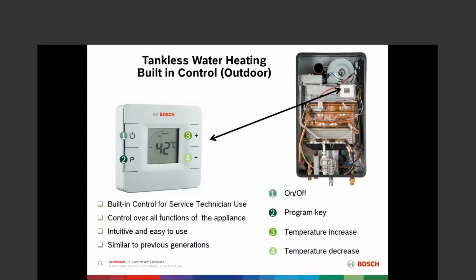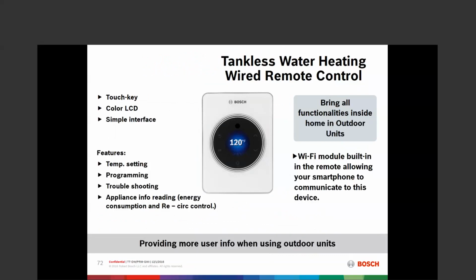This is the control on the outdoor unit and the display for the outdoor unit. You can see it's not nearly as friendly as the indoor unit control. It gives just about all the same functionalities. It does not give solutions on error codes. It gives just the error code. But again, for the outdoor unit, if somebody wants that full functionality, you just get that optional touchscreen display. It's wired. That optional wired display looks like this.